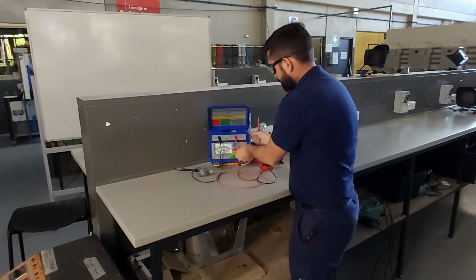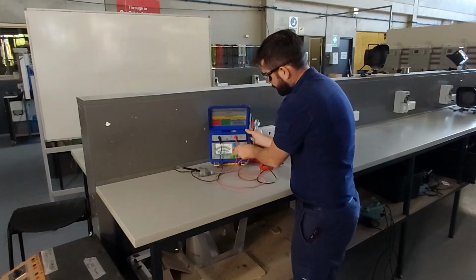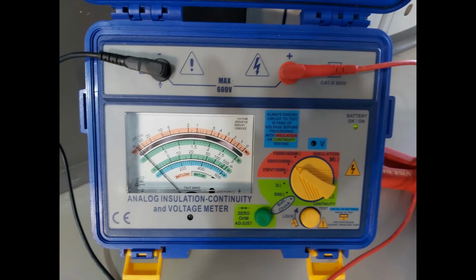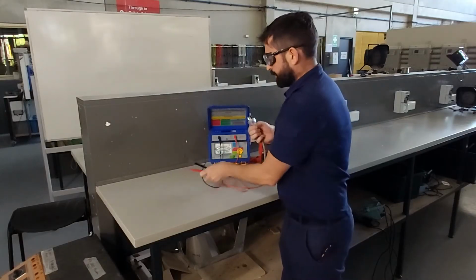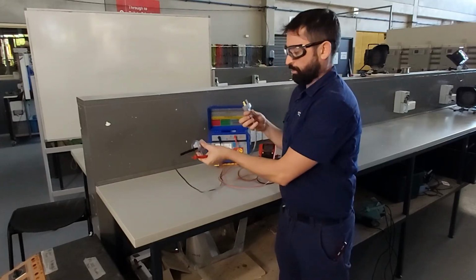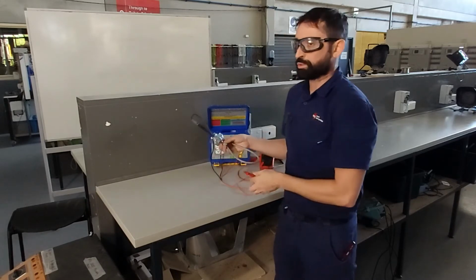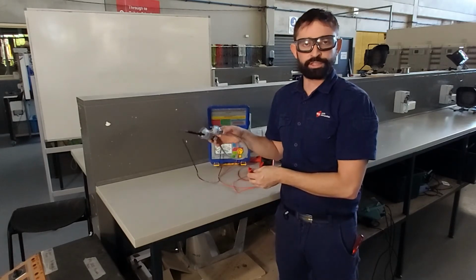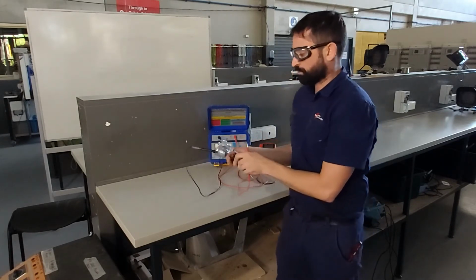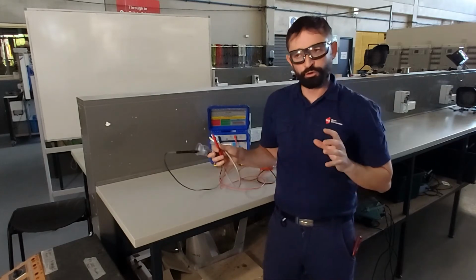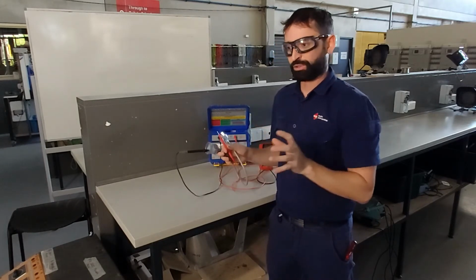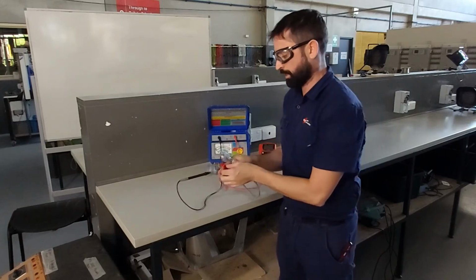Now we're going to turn our insulation resistance tester up to 500 volts. Alright, so we know this extension cord is going to take 240 volts. So what we usually do is a little over double what it's usually going to take. So we're going to do 500 volts. The reason why we do 500 volts is because we want to put enough pressure on it in extreme circumstances. We want to see if any of the current's going to leak out.